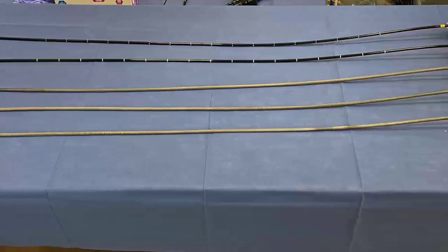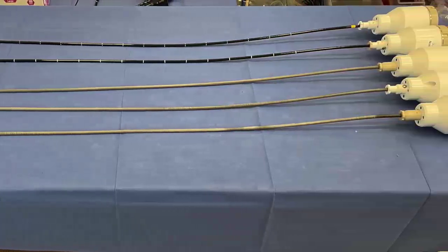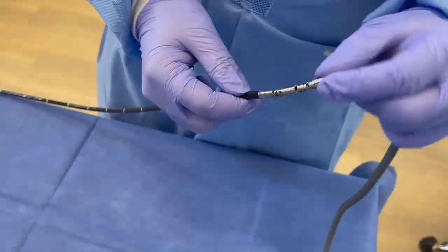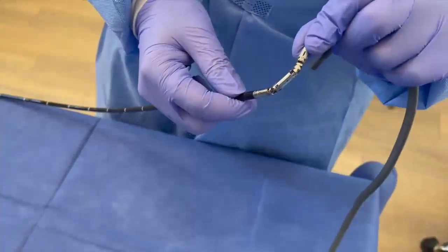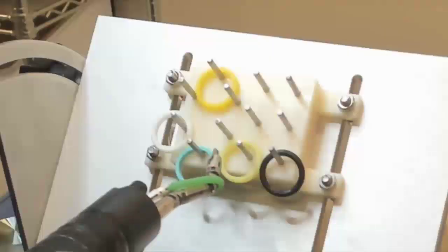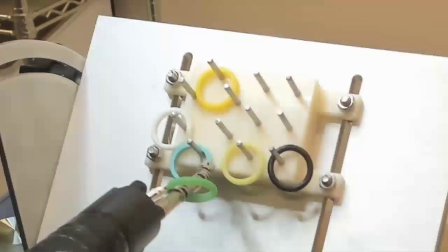There are six different classes of surgical instruments which can be inserted into the two working channels of the robotic endoscope. All instruments have articulation and triangulation capabilities that enable movements in seven degrees of freedom. Importantly, all instruments are robotically controlled.